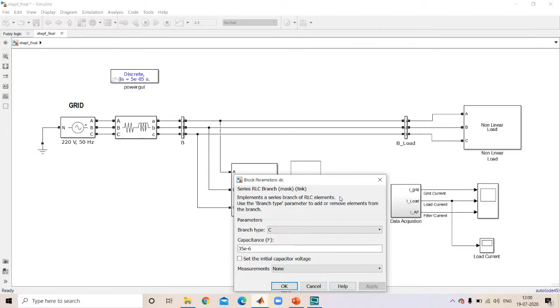Normally in domestic applications, in all our loads, even if we have 48.43% harmonics, we still use those loads, but the long life of the product will be very less. As per IEEE standards, we need to maintain the harmonic distortion in any product at 5% only. But we are using up to 48% also at our home. As per IEEE standards, whatever product we are developing, we need to maintain its harmonic distortion at 5% only.